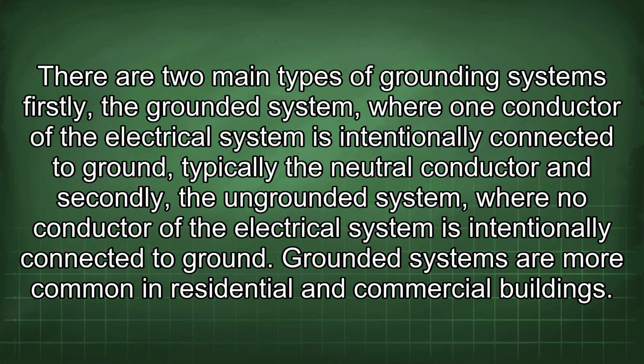There are two main types of grounding systems. Firstly, the grounded system, where one conductor of the electrical system is intentionally connected to ground, typically the neutral conductor, and secondly, the ungrounded system, where no conductor of the electrical system is intentionally connected to ground. Grounded systems are more common in residential and commercial buildings.